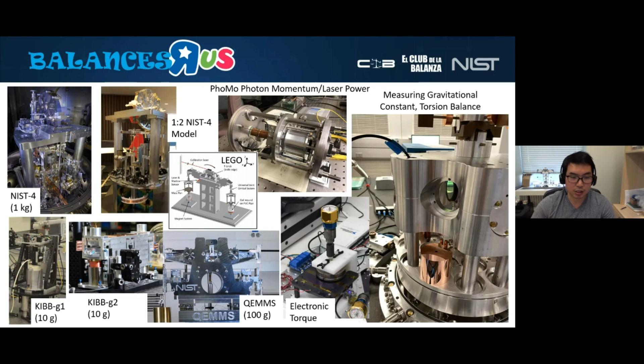So here's the present state of mass dissemination in the US. Say you're a mass metrologist and you want to use a 1 gram calibration weight to calibrate your analytical balance or your mass comparator. How do you know your 1 gram mass is actually 1 gram? Well, in principle, it starts with you shipping your mass set, which around here ranges from 1 milligram up to 20 kilograms. So there's this big wooden box that weighs over 40 kilograms total, and you have to ship this to NIST. On our end, we start with the top of the traceability chain using the NIST 4 Kibble balance. And then this instrument assigns value to the kilogram artifact with about 10 parts per billion uncertainty.